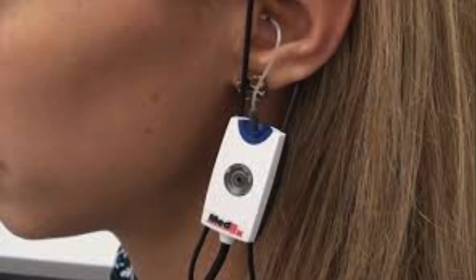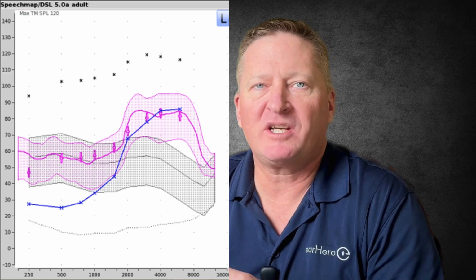Real ear measurement is sometimes called REM or probe mic testing. It's the only real way to verify how a hearing aid is performing inside your ear. Here's what happens. A tiny microphone is placed gently inside your ear canal. Don't worry, it's a tiny, soft little tube, and you won't even know it's there. You will hear some calibration sounds, and your provider should tell you to remain quiet to get the correct readings. The hearing aid goes on top of it, and speech-like sounds are played through a speaker. The system measures in real time exactly how much sound reaches your eardrum at every one of the frequencies. Not what the software predicts, not what the manufacturer assumes, but what's actually happening in your ear. This turns hearing aid fitting from an opinion into a science.